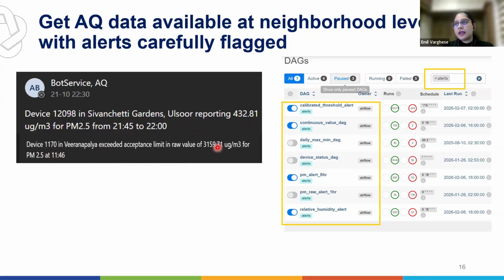This tells us that this is actually an invalid point, because this has already exceeded the raw value from the raw table, or the 1-minute standardized table that we pushed. This means the sensor has gone bad, because the sensor was only able to detect up to 1,000 micrograms per meter cube, but it's reporting 3,000, which means the sensor has gone bad.